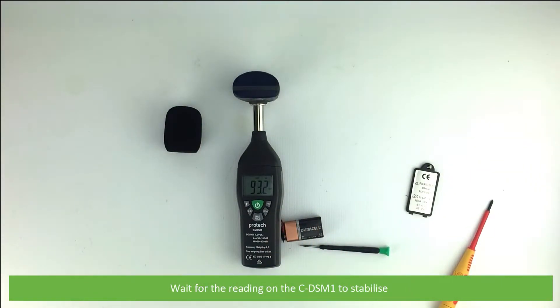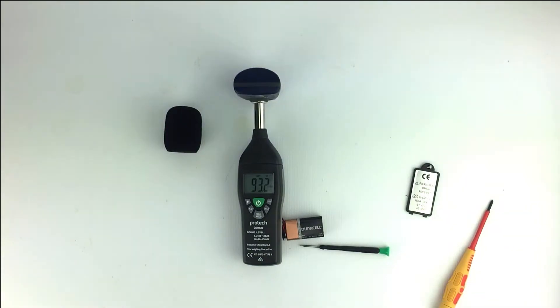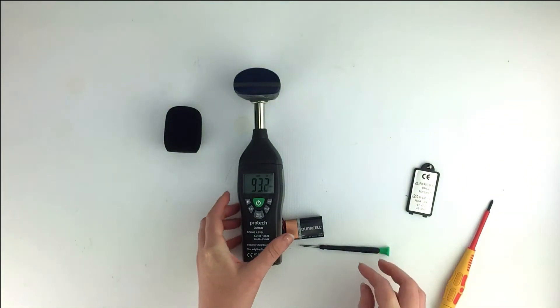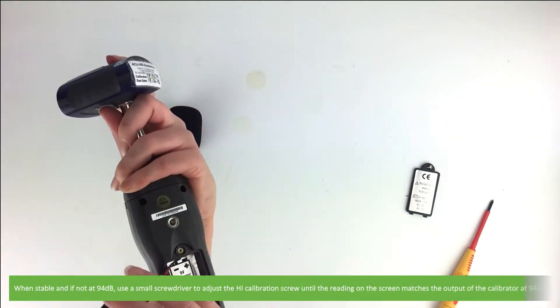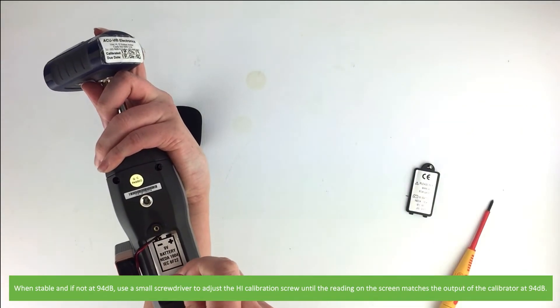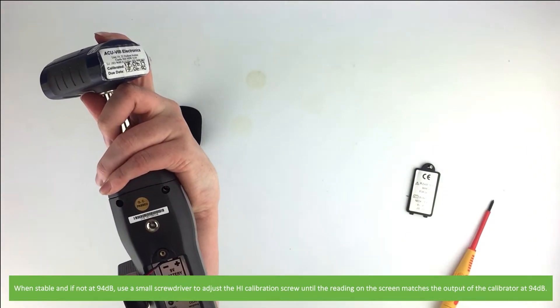Wait for the reading on the CDSM1 to stabilize. When stable and if not at 94 decibels, use a small screwdriver to adjust the high calibration screw until the reading on the screen matches the calibrator's output of 94 decibels.